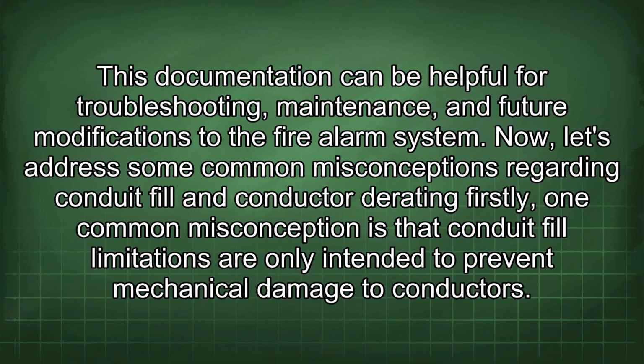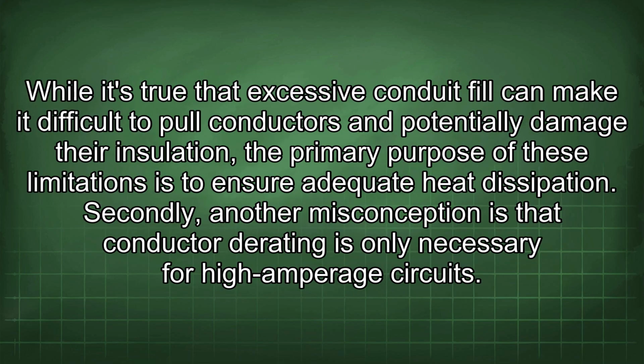Now, let's address some common misconceptions regarding conduit fill and conductor derating. Firstly, one common misconception is that conduit fill limitations are only intended to prevent mechanical damage to conductors. While it's true that excessive conduit fill can make it difficult to pull conductors and potentially damage their insulation, the primary purpose of these limitations is to ensure adequate heat dissipation.